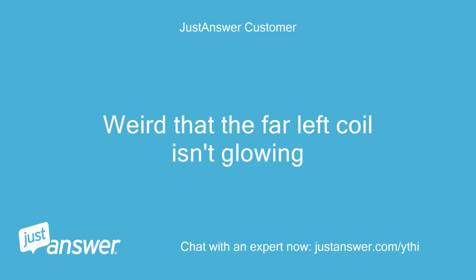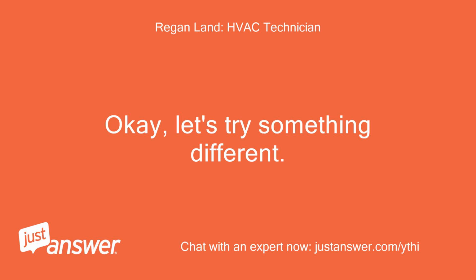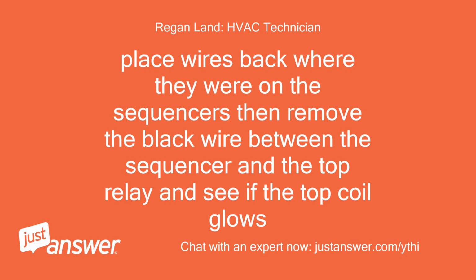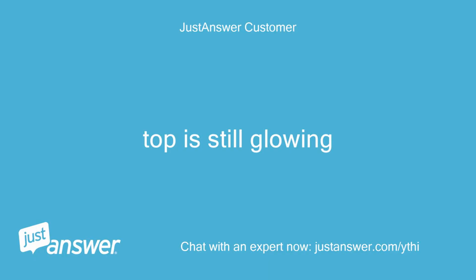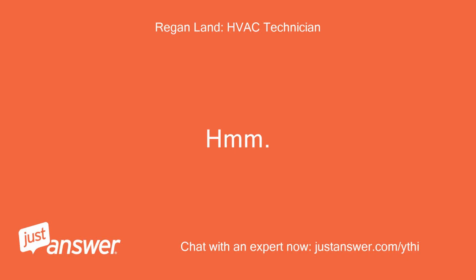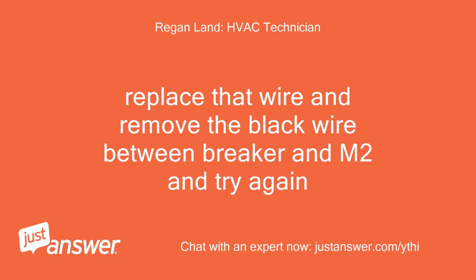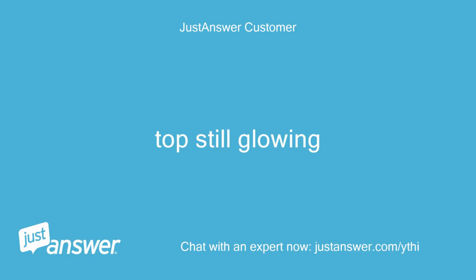Okay, let's try something different. Place wires back where they were on the sequencers, then remove the black wire between the sequencer and the top relay and see if the top coil glows. Top is still glowing. Replace that wire and remove the black wire between breaker and M2 and try again. Top still glowing.